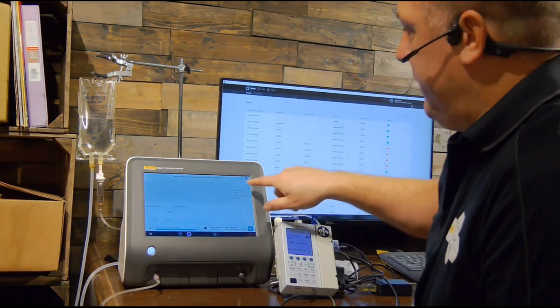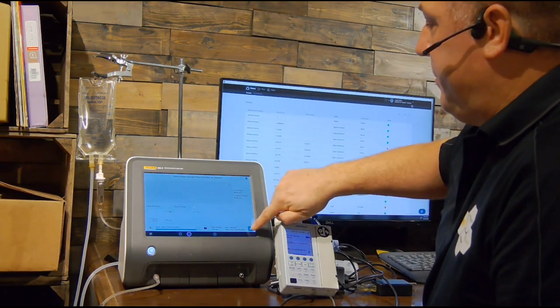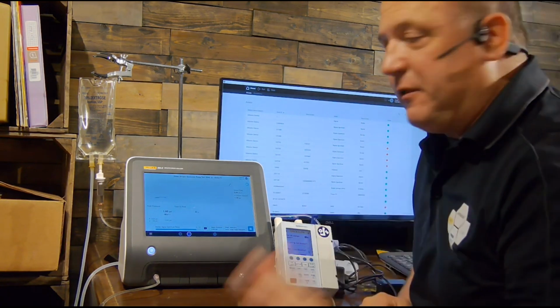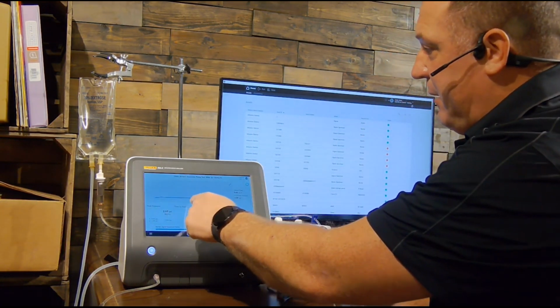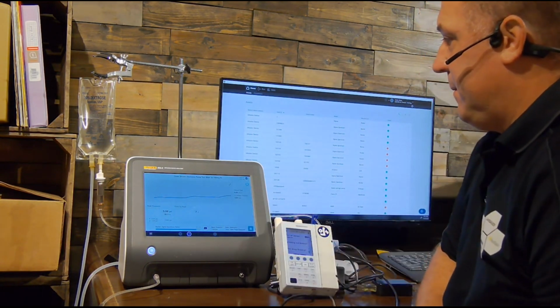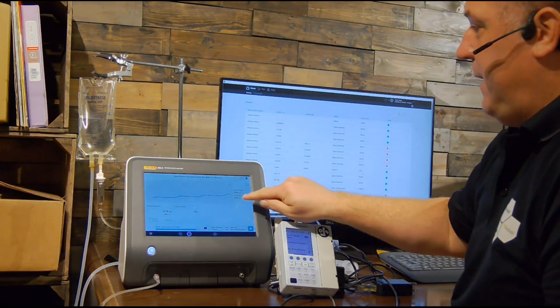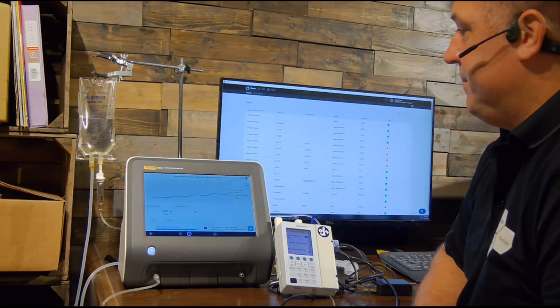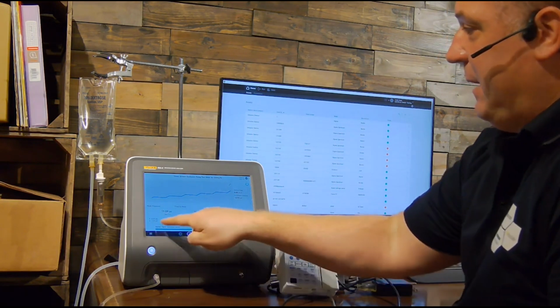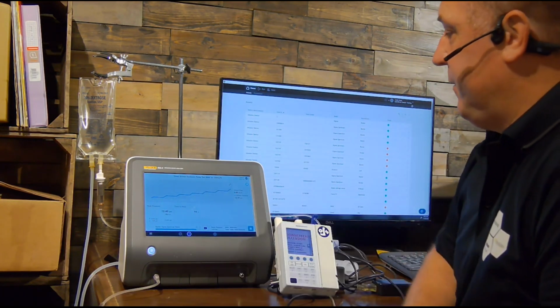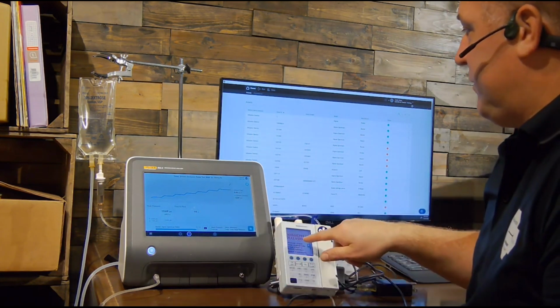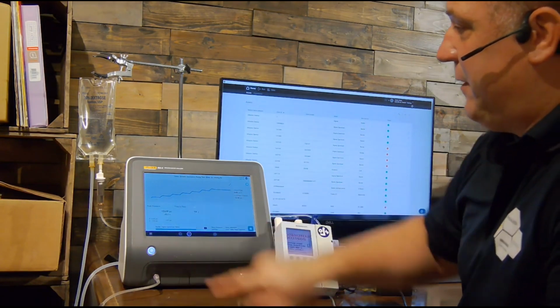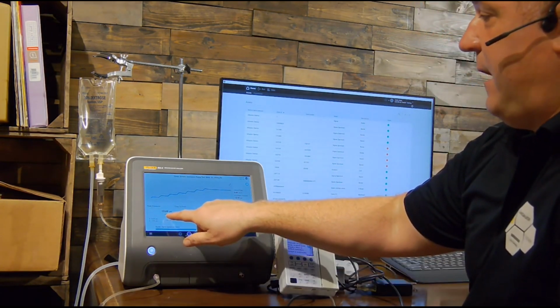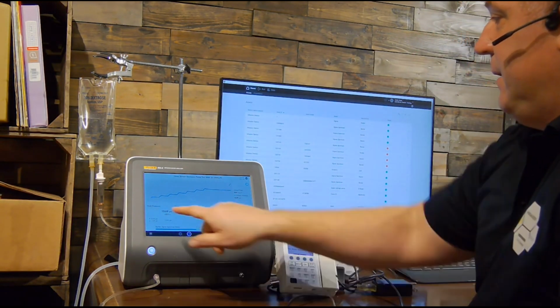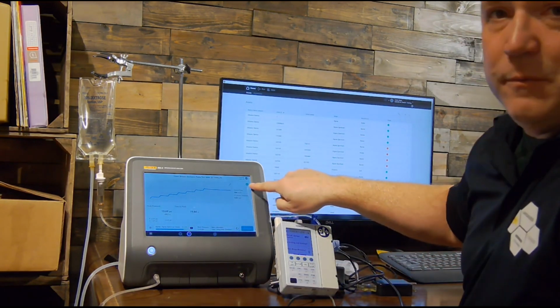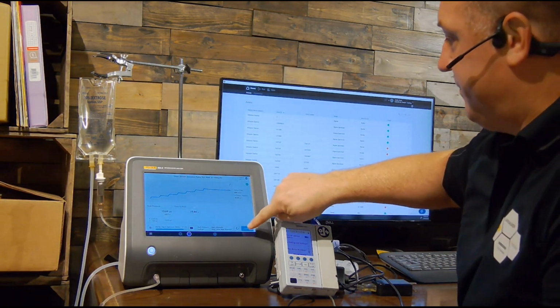Now what I want to do is make sure I get a flow established first. And I'm going to go ahead and push play. Now my test is running, and you'll see my pressure here, and my pressure is going to start to increase. I'm up to 7.39 psi, 9.81, and I have my limits programmed right into here. My time to peak so far, it took 19 seconds there. Here's my occlusion here. My peak pressure is 13.69 psi, or a plus 5.3% tolerance from where we had it. It's within passing score, and there's my passing result, the green arrow dot right here. So I'm going to push continue.